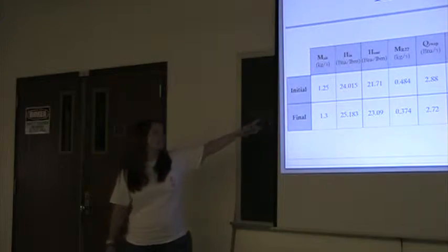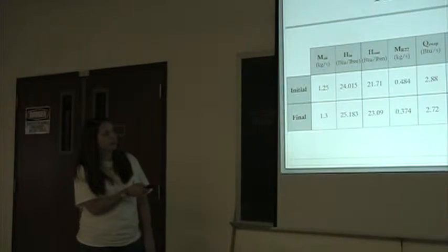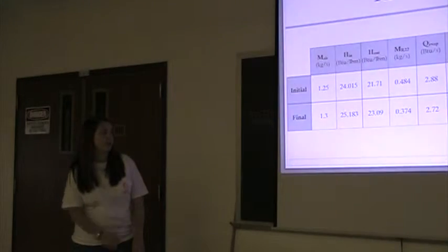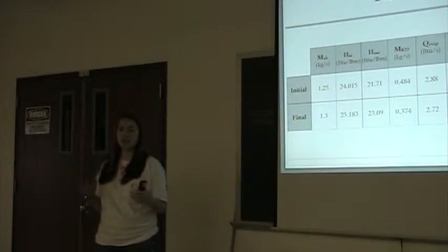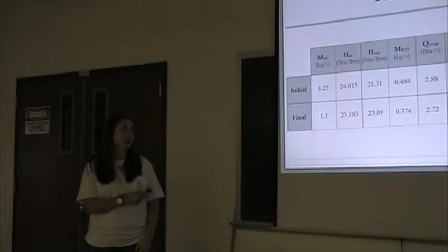So these are the results from that. You can see I did it for initial and final, and it didn't vary that much. I got a total tonnage for the initial at 0.86 and for final 0.81. And I researched that for a residential house or whatnot, tonnage for an evaporator is usually around 1 to 5, so it wasn't that off.